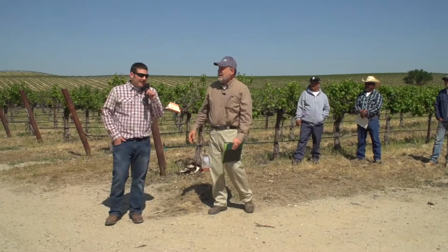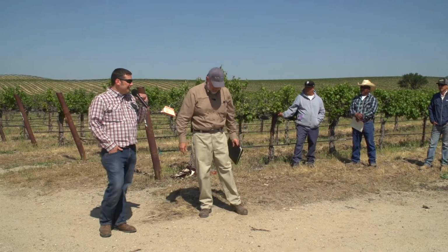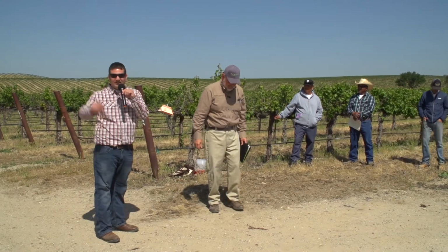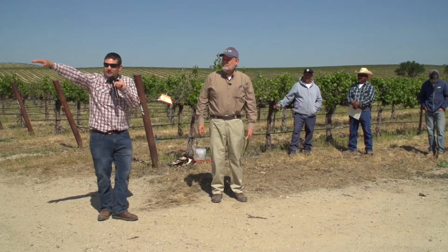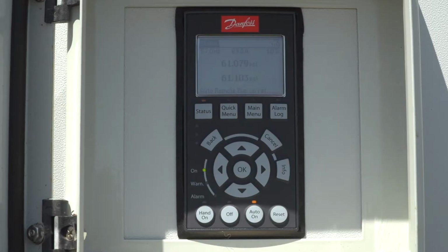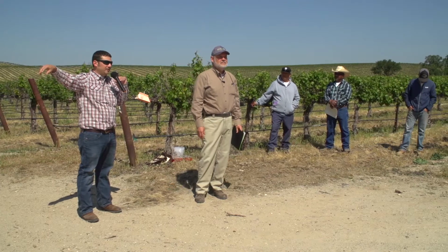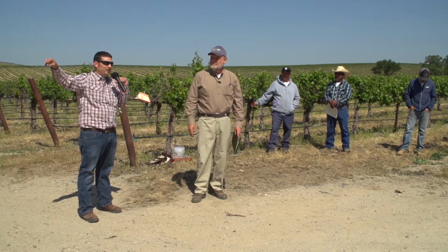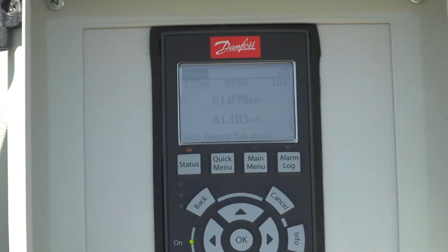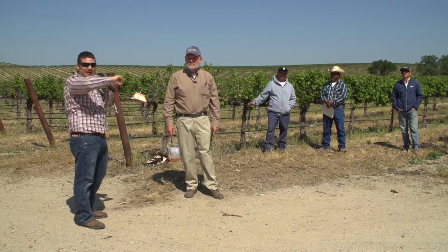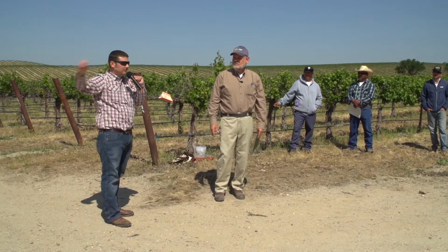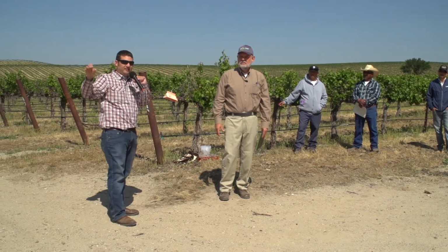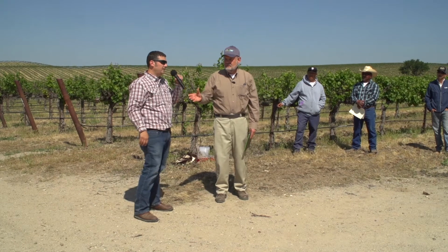Yeah, so the reason why we want to use a VFD, and a good reason why it works maybe in a field like this, is when we have different size irrigation sets, we can control the pressure to the set that we want to hit. So instead of running full open to hit that farthest part of the vineyard and having that be the same pressure up here, we can actually adjust the pressure to optimize and save energy for each set.